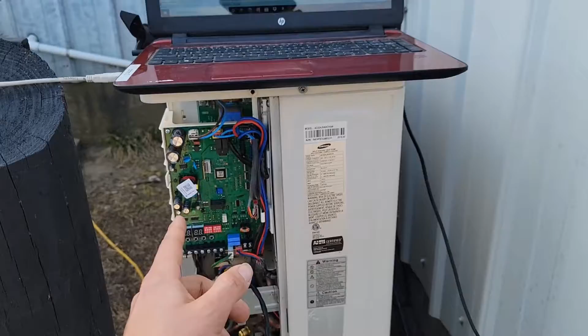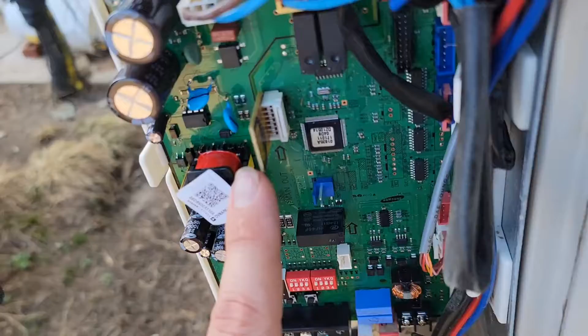With this system here, I changed the outdoor board. When you change a board on a Samsung unit, if you don't order a pre-programmed EEPROM, you may need to program the EEPROM yourself. So I want to tell you how to program the EEPROM for an outdoor unit.